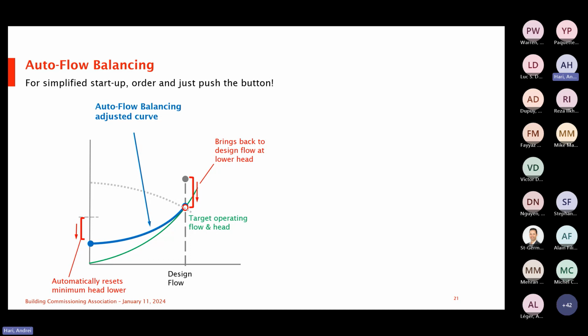So what we're able to do now is, instead of being fixated on one DP sensor, we can consistently adjust right at the control card, right across the board. And that's the beauty of this. Now, this is just a 45-minute, 1-hour presentation on the technology. But if anybody wants to do a deeper dive into it, I'd be more than happy to spend more time with you, because this is where it differentiates how we're pursuing systems today. And then all of a sudden, it really becomes more of an energy conversation in our design philosophies and how we're moving BTUs in the system.